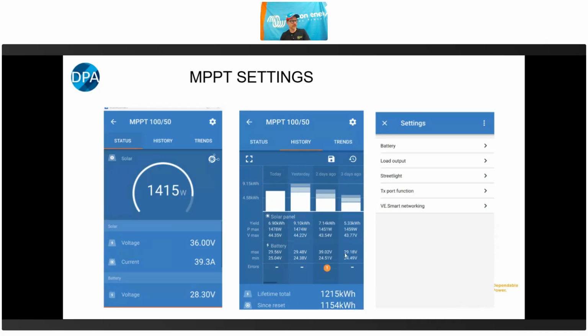On the right-hand side, you've got the history tab. This is quite similar to what I was talking about with the battery monitor. You can see the minimum and maximum battery voltage for each day, and that's really useful for troubleshooting. And then you've got what the maximum yield has been for each day, so the total it put out, and what the maximum the panel actually put out on each day.